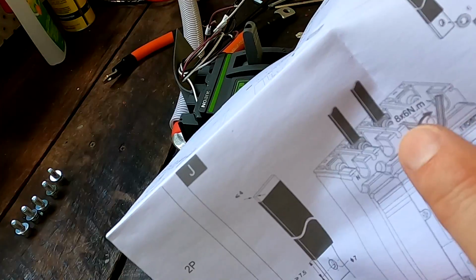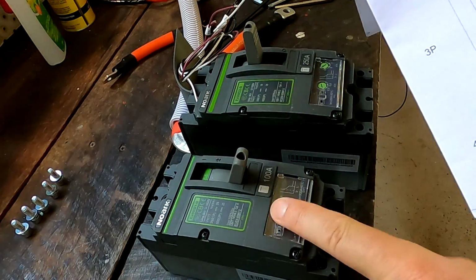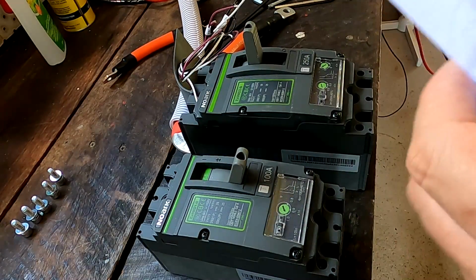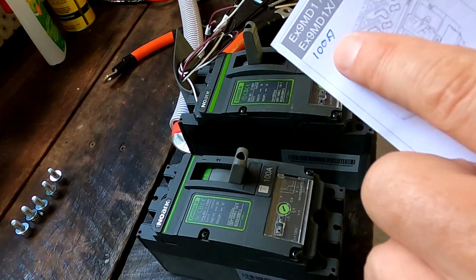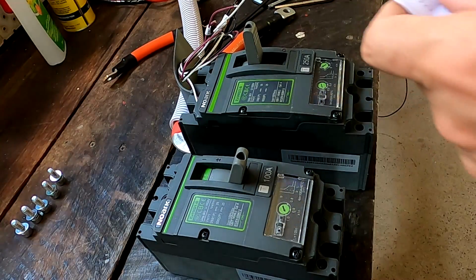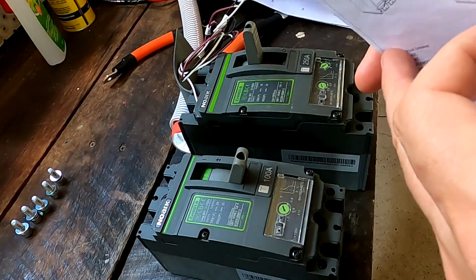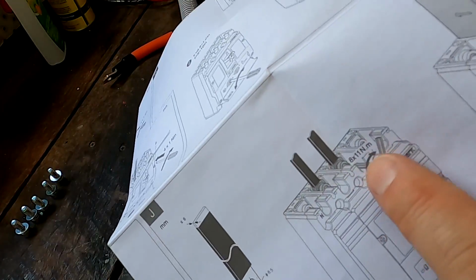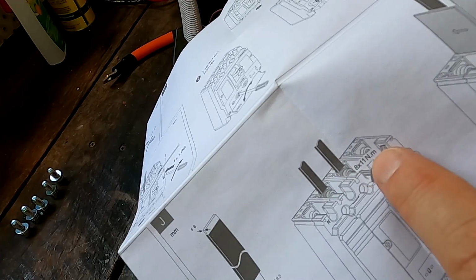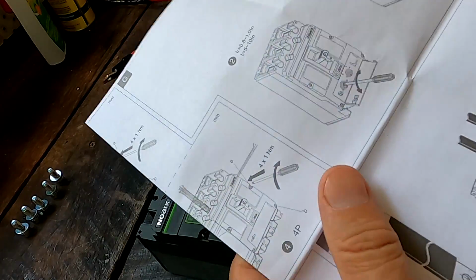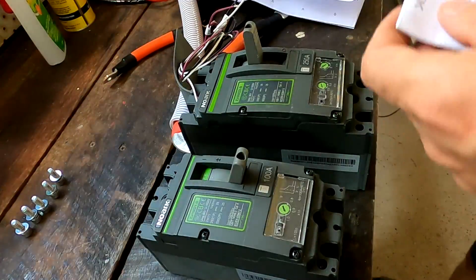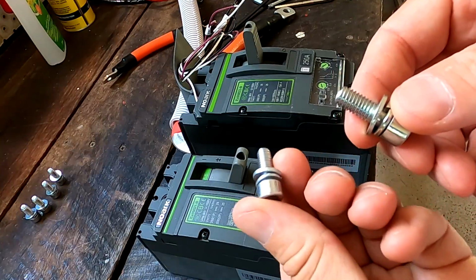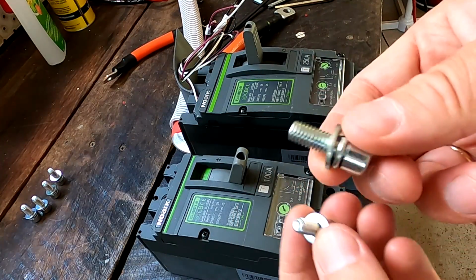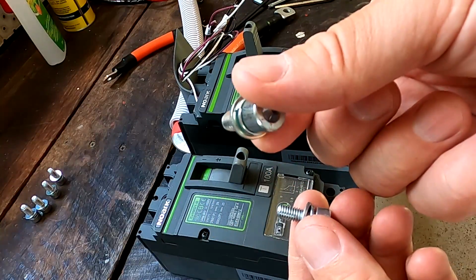The torque setting for the terminals of the smaller 100 amp circuit breakers is lower. These are the 100 amp breakers. The larger 250 amp breaker has a torque setting of 11 Newton-meters. That's quite a big difference, right? We've got M6 and M8—6 Newton-meters and 11 Newton-meters.